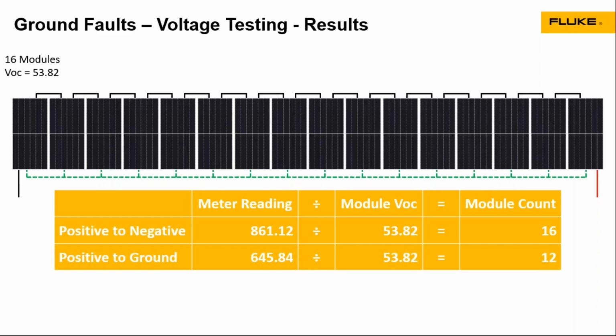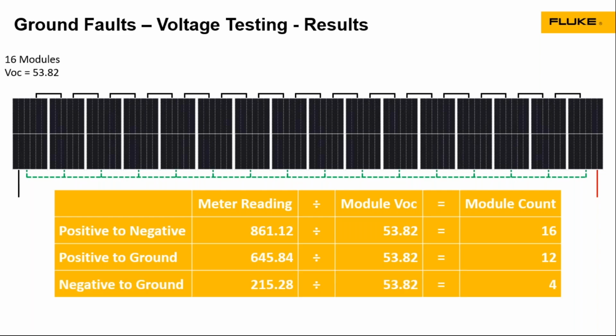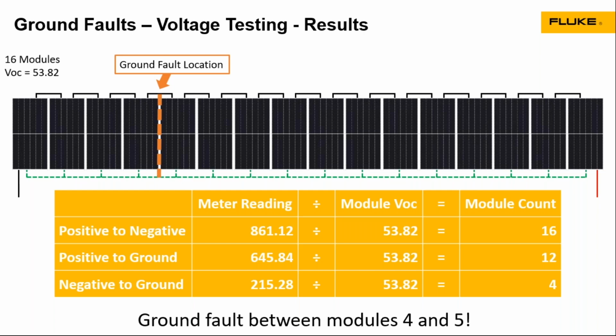Testing from positive to ground, I got 645 volts. I expected 0. When I divide that by 53, I get 12 modules. And my negative to ground, I expected 0. I got 215. Divide that by 53, and I get 4 modules. What this tells me is that between the positive and the ground fault, there are 12 modules, and from the negative to the ground fault, there are 4 modules. So if I measure in from the negative side of the string, I expect to find the ground fault between modules 4 and 5. That's because negative to ground, I'm reading the voltage of 4 modules, and positive to ground, I'm reading the voltage of 12 modules.